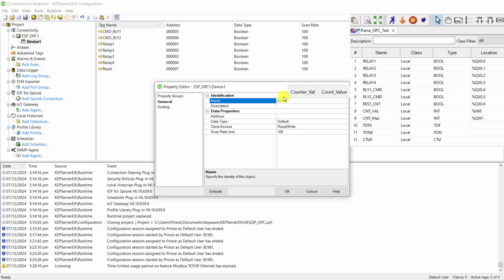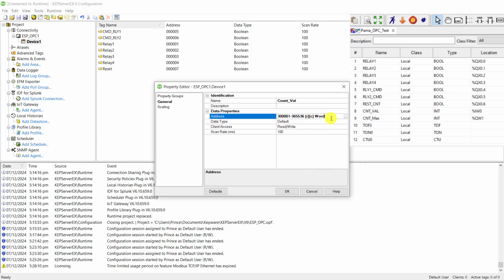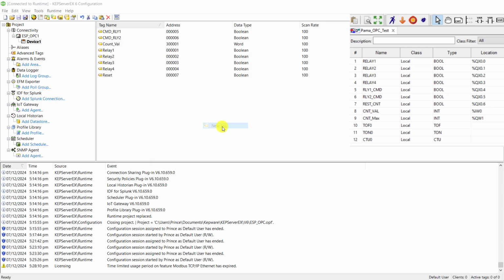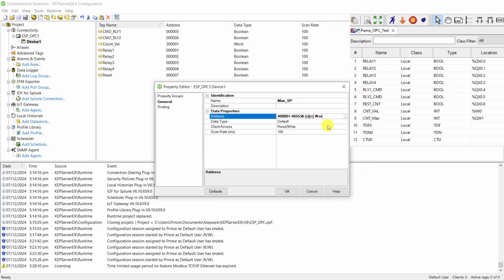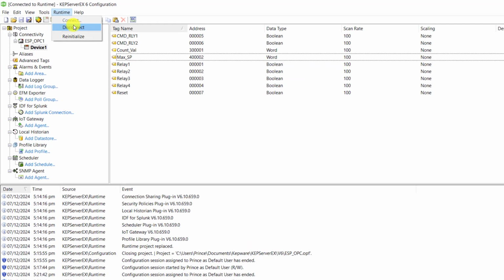We now move on and add our variable. So this is our count variable, and this is a read variable that is going to be our input. Integer is starting from 30,000. Okay, and now I add the holding register. And this we shift, and this is going to be 400002 because our address is 2. Okay, great. So we can see all our tags are ready.